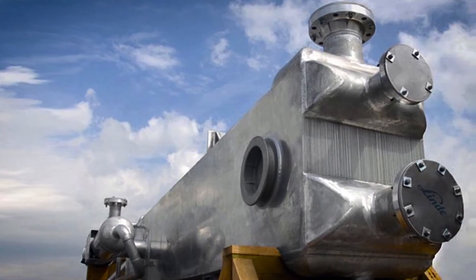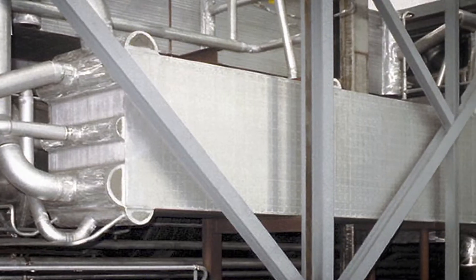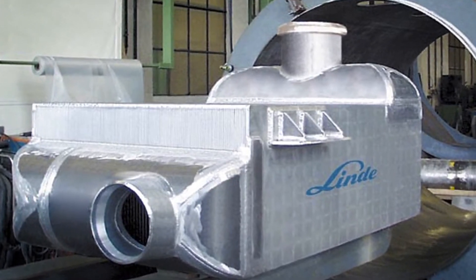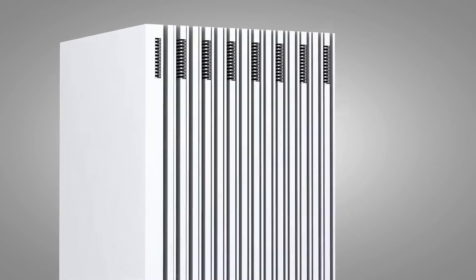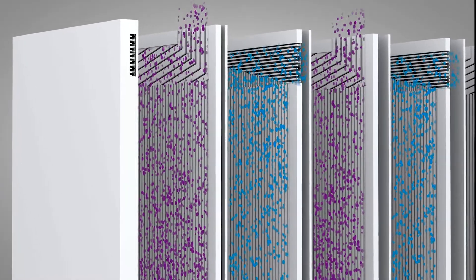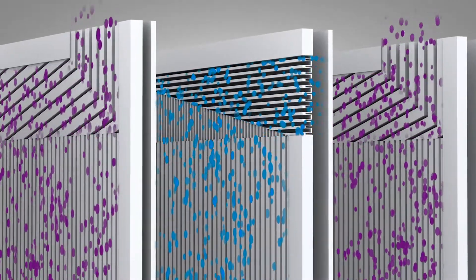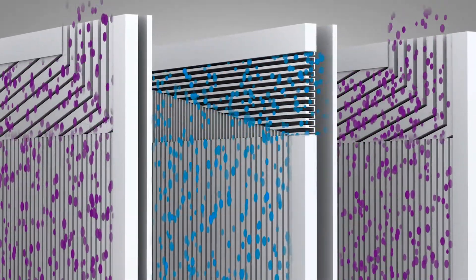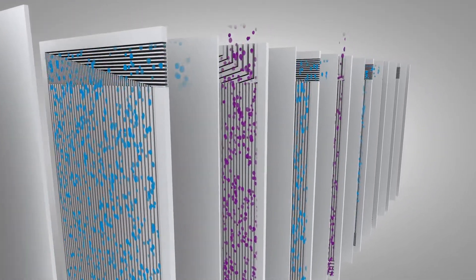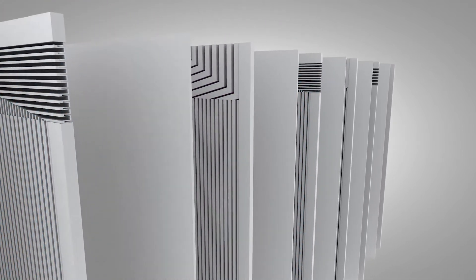The other widely used LNG exchanger is the plate fin type. They're smaller and lighter than coil wound exchangers, and we can easily scale them from small to large sizes. Fluids move through alternating layers of corrugated fins separated by flat plates, transferring heat between natural gas and refrigerants. Those fins enhance heat transfer from the fluid, and they conduct more heat directly into the plates. These layers of fins and plates can be combined in many configurations to optimize heat transfer.